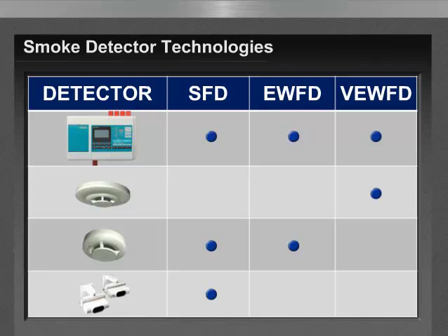And with this specific category of detector technology, we'll see it line up in the standard fire detection and early warning fire detection categories, largely based on its sensitivity characteristics and ability to perform its intended function at those sensitivity ratings. And the next on the list is laser spot type smoke detection. And this category of detection is as well a passive spot type detector. Its sensitivity capabilities will allow its operation within the very early warning fire detection mode. Now, you won't see it checked off in the other categories because of its sensitivity characteristics, so it remains in the very early warning fire detection category.